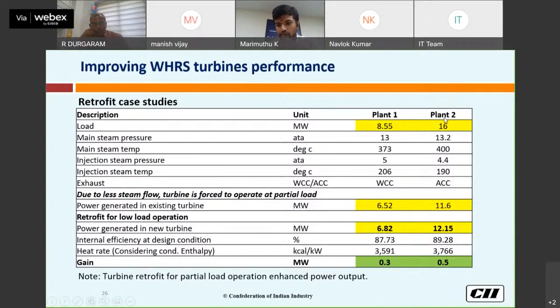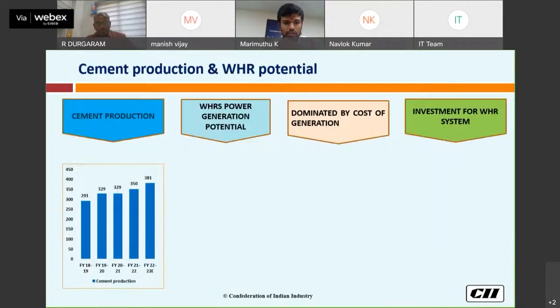So there, a gain of around 0.3 megawatt was achieved. In the case of plant 2, 16 was the design, and they were operating at 11.6. To increase the internal efficiency, the retrofit was done, and it has increased around 0.5 megawatt. So what I am coming to say is, with the latest technology, there are options to increase the existing turbine efficiency by 2 to 6%.